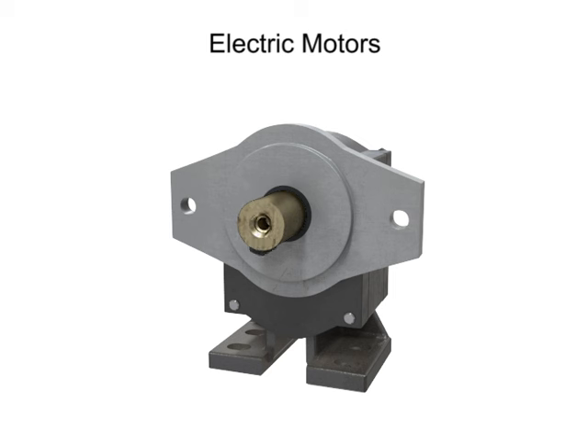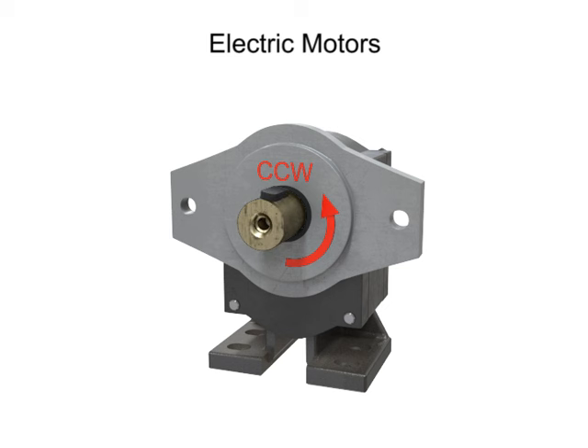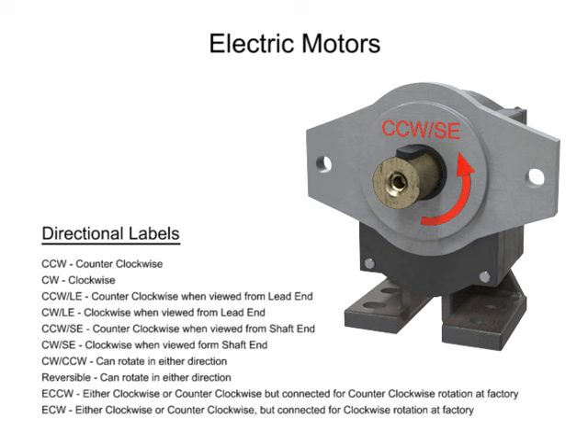By contrast, the rotational direction for hydraulic pumps is specified as clockwise or counterclockwise rotation when viewed from the shaft end. Manufacturers use different descriptions to label both motors and pumps; some standard labeling conventions are shown here. If a motor or pump is not labeled on the frame, consult the manufacturer for specifications.